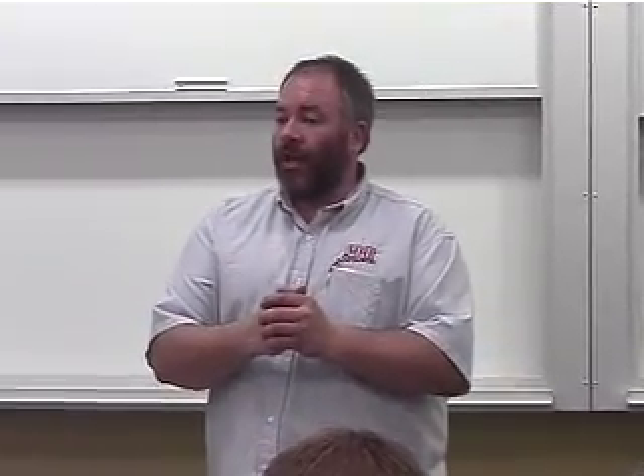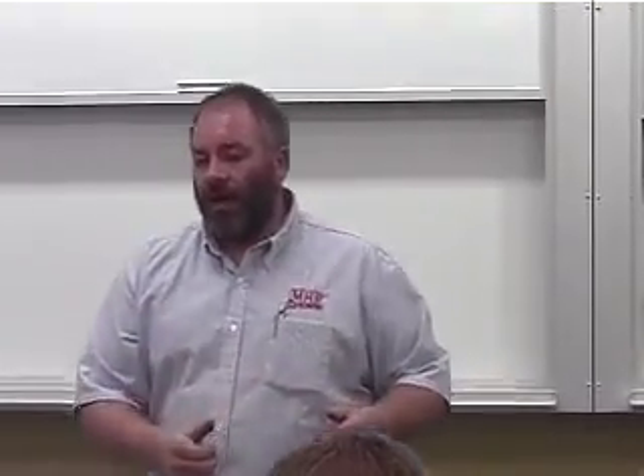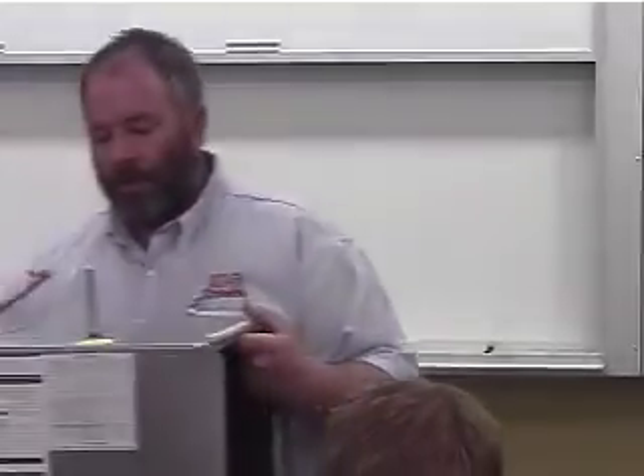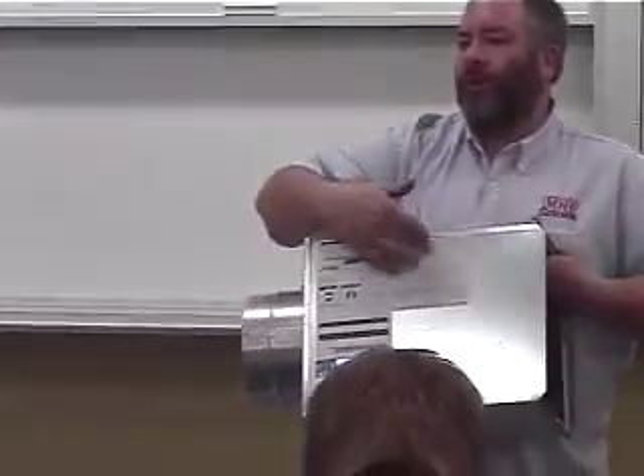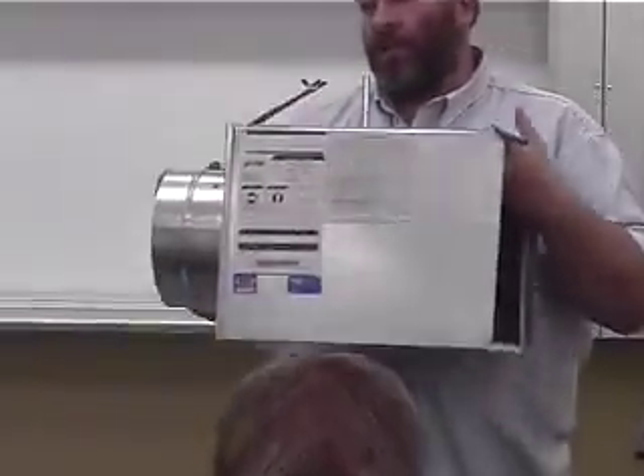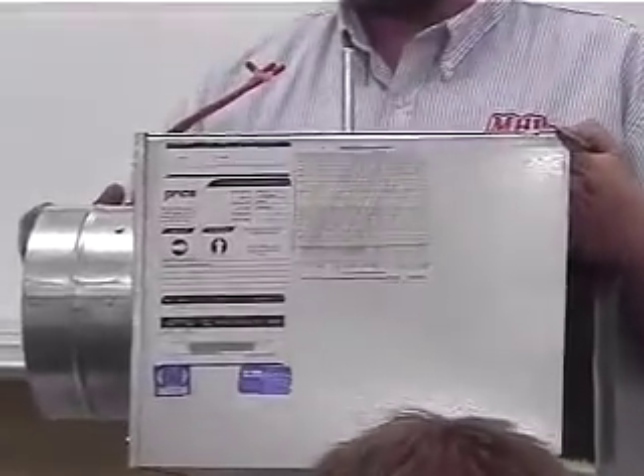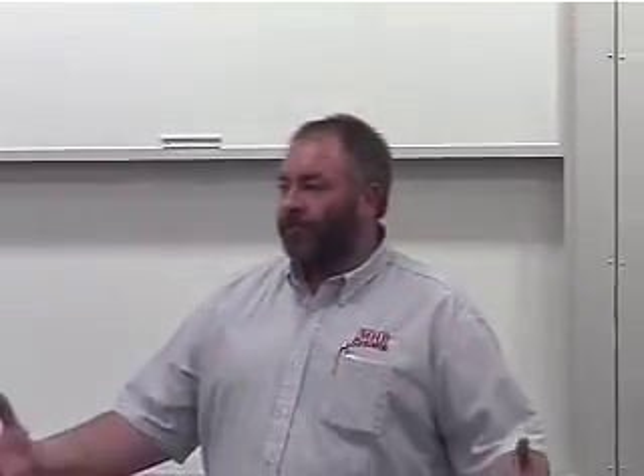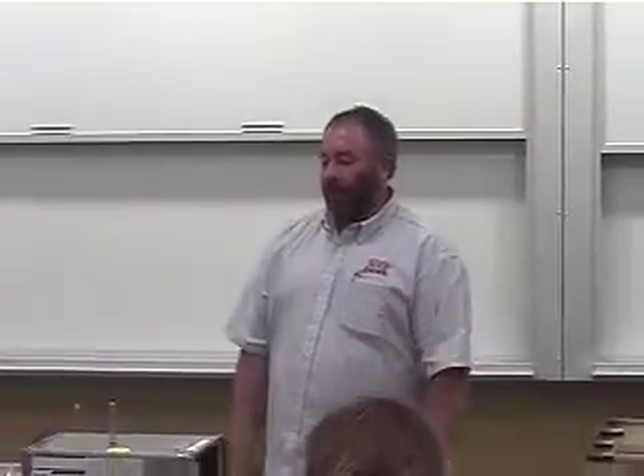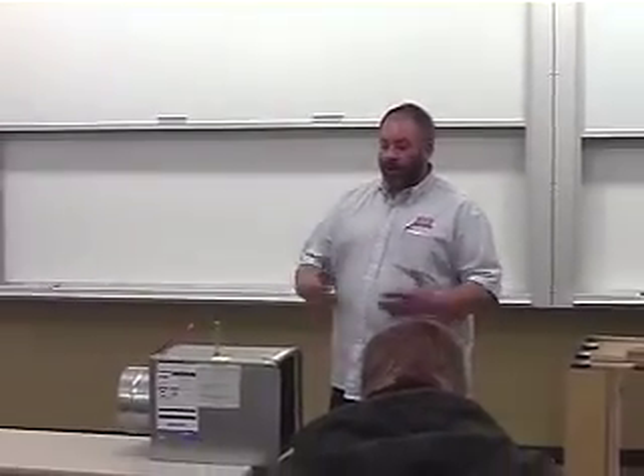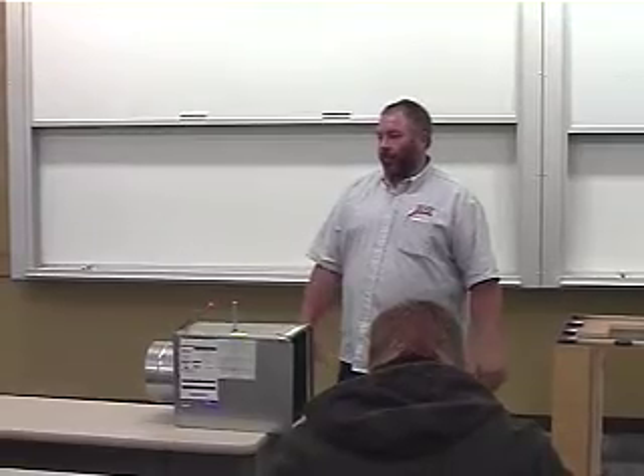Boy, I don't know if there's anything else. Every VAV is designed for a specific size. Here on the side of the box, you notice there's a chart. For specific CFMs, you need to put a specific box in to be able to move that CFM. Same thing with his Phoenix valves he was talking about. You can't take a 4-inch valve and move the same amount of air you're going to move through a 12-inch box. So, that's all there is to it, is make sure you get the right box. That's the engineer's job, that's what he's supposed to do.